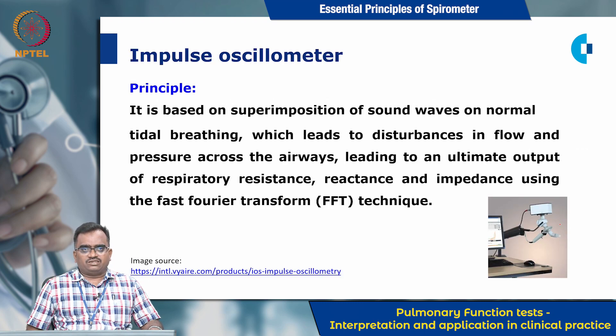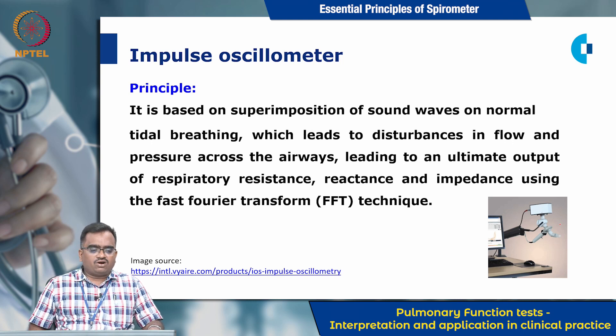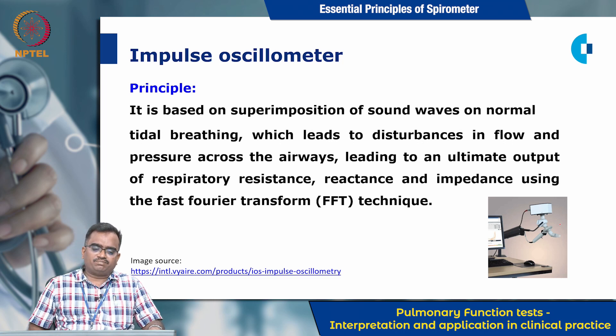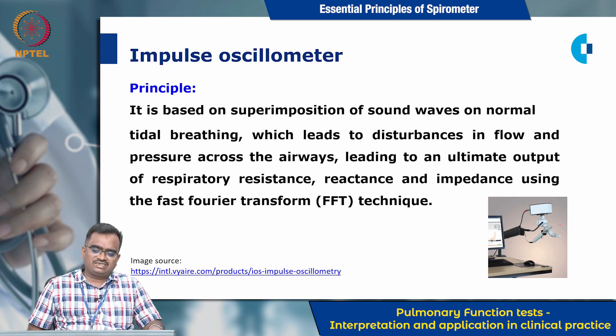The next device is the impulse oscillometer, which is based on the superimposition of sound waves on normal tidal breathing. This leads to disturbances in flow and pressure across the airways, producing an output of respiratory resistance, reactance, and impedance using the FFT technique.